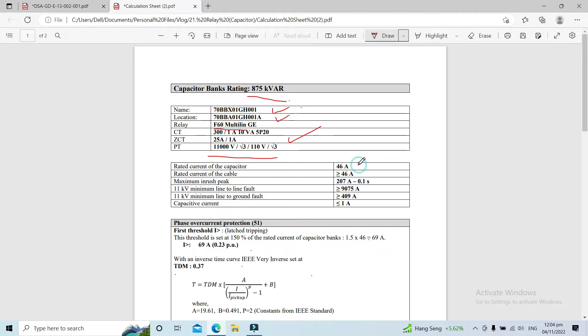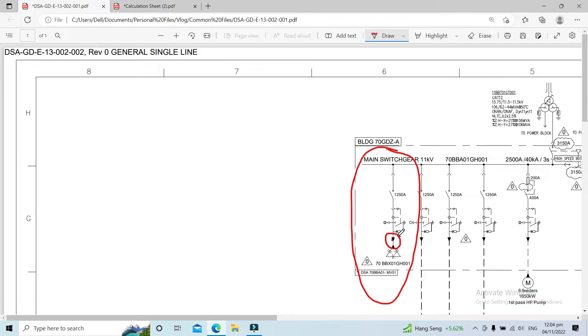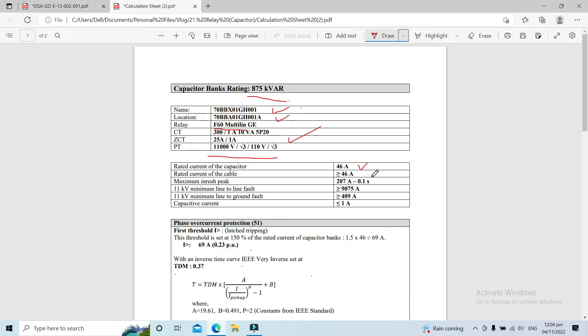Our capacitor is rated at 46 ampere, and the rating current of the cable is above 46 ampere. The maximum inrush peak current of our capacitor bank is 207 ampere at 0.1 second. The 11 kV minimum line-to-line fault current is greater than or equal to 9,075 ampere, and the capacitive current of our cable is less than or equal to 1 ampere.